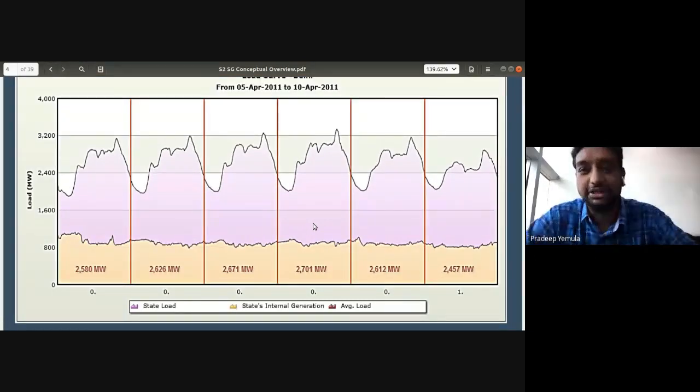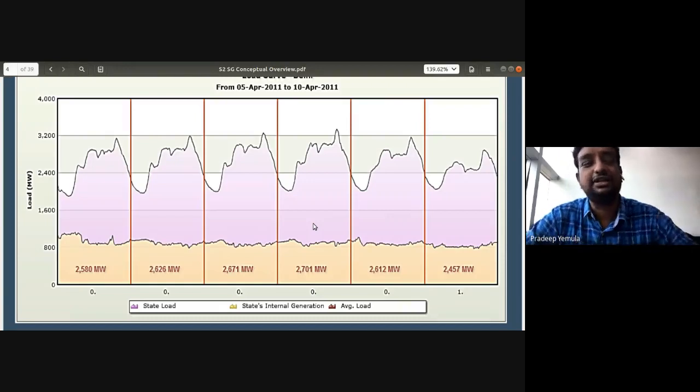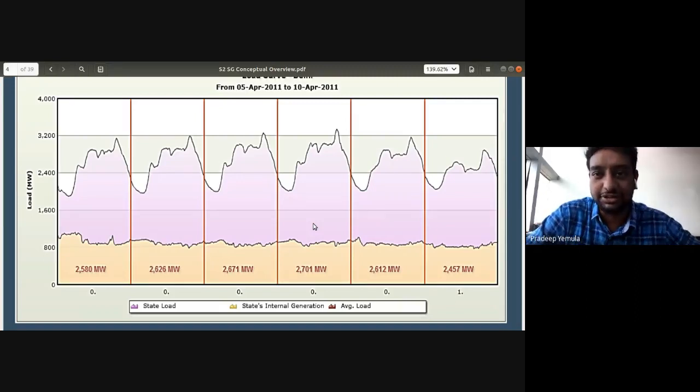There is an operation center. They are continuously monitoring. They keep sensors at all substations and get continuously monitored data. If they notice that the load is increasing, then they increase the generation. So obviously the overall generation capacity should be there. But then which generator to switch on and which to switch off, the decision of committing the generators, that decision has to be made.